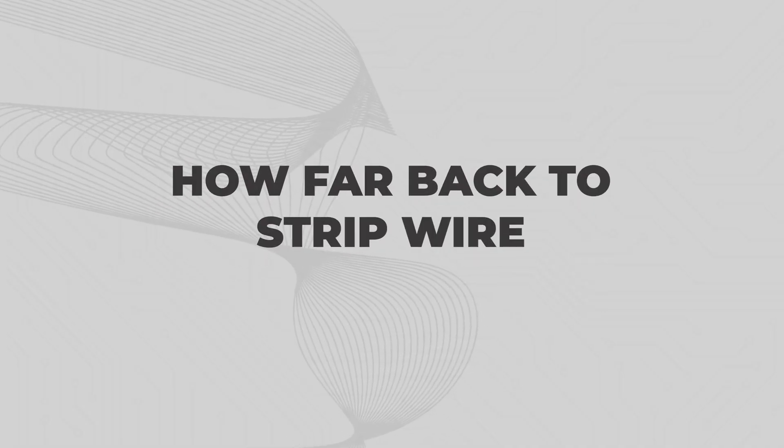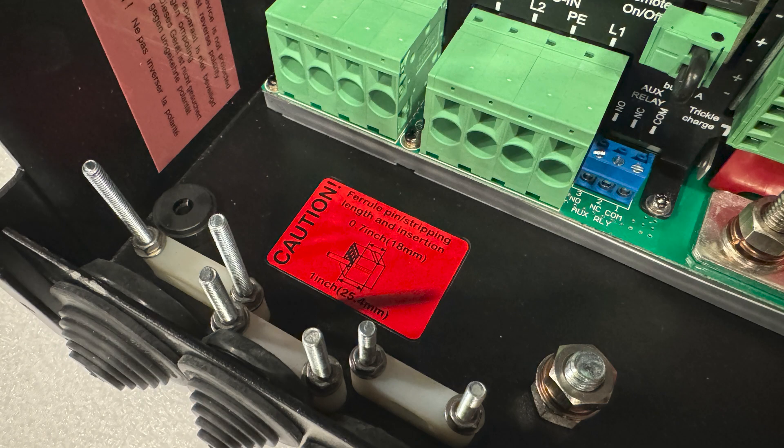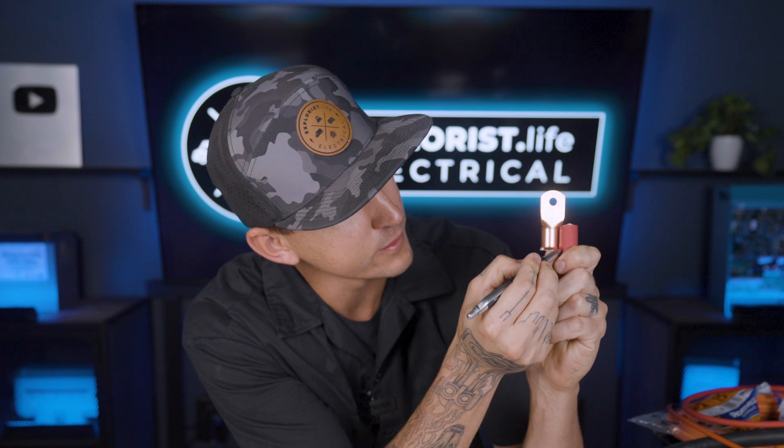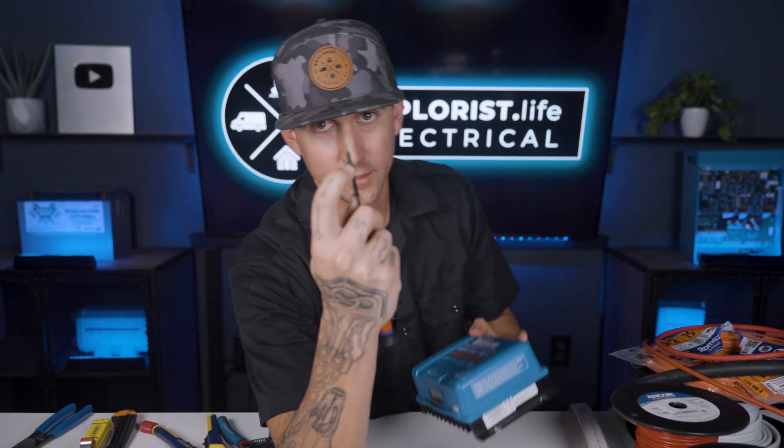How far back to strip wire? There's no one right answer because it really just depends on what component you're connecting it to, but here are some helpful tips. Sometimes the user manual or the actual component will tell you how far back to strip the insulation. If neither of those are options, use the physical barrel length of whatever terminal you're using and a pen to mark where the insulation should be stripped to. For a screw terminal where you're not using a ferrule, stick a screwdriver into the powered-off component, measure with your finger, and transcribe that mark to the wire.